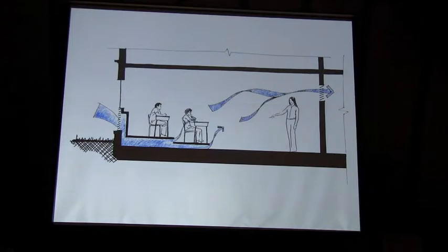And this idea of night flush, even though there's people in this picture, pretend it's a night class. So louvers are opened up on a hot day when outside air in a place like Eugene is much cooler than it is inside the building because of the hot air that was left over. Cool air gets moved through passively, takes heat off of the mass of the building, and then that air leaves, right? So you're getting a lot of unfiltered outdoor air in a building like this. So this is called night flush, and this is something that I'll bring up a couple more times.